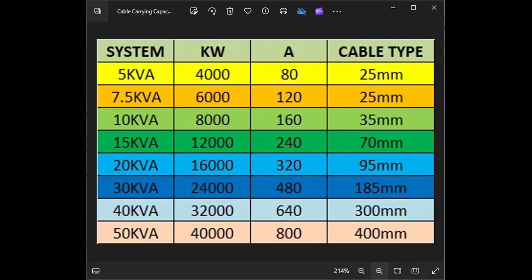So if we're looking for cable sizing, for a 5 kVA system we actually go for 25 mm for the battery to inverter connection. I think for the load we just calculated, the inverter is supposed to be around 2 kVA or 1.5 kVA, and the maximum current that will be flowing from the battery to the inverter and vice versa is 30 amps. So typically, in that case, a 16 mm cable can work.